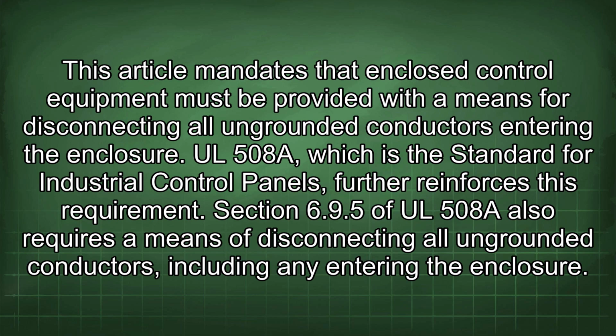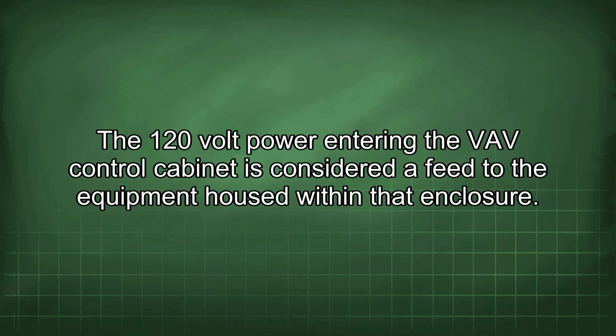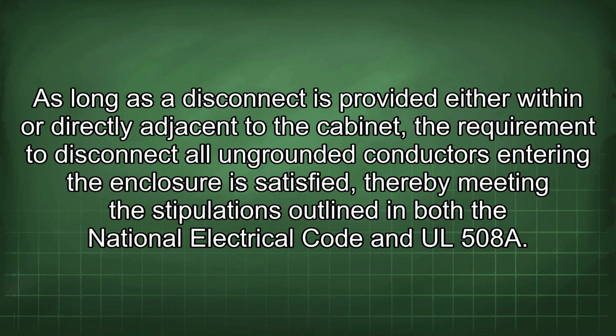Section 6.95 of UL 508A also requires a means of disconnecting all ungrounded conductors, including any entering the enclosure. The 120 volt power entering the VAV control cabinet is considered a feed to the equipment housed within that enclosure. As long as a disconnect is provided either within or directly adjacent to the cabinet, the requirement to disconnect all ungrounded conductors entering the enclosure is satisfied, thereby meeting the stipulations outlined in both the National Electrical Code and UL 508A.